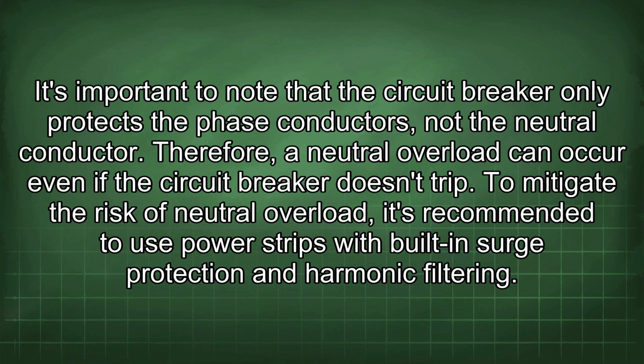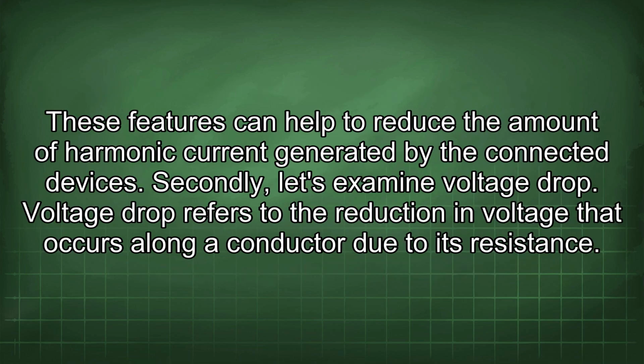It's important to note that the circuit breaker only protects the phase conductors, not the neutral conductor. Therefore, a neutral overload can occur even if the circuit breaker doesn't trip. To mitigate the risk of neutral overload, it's recommended to use power strips with built-in surge protection and harmonic filtering. These features can help to reduce the amount of harmonic current generated by the connected devices. Secondly, let's examine voltage drop.